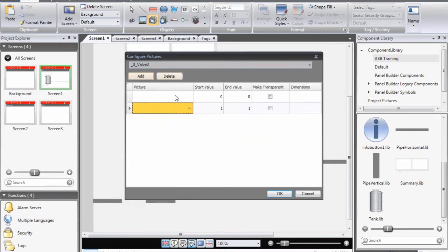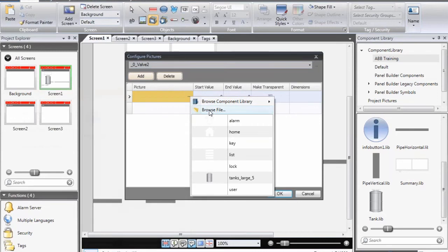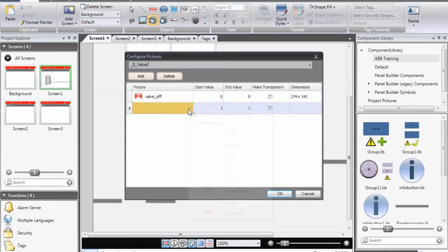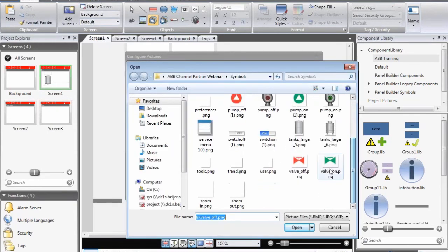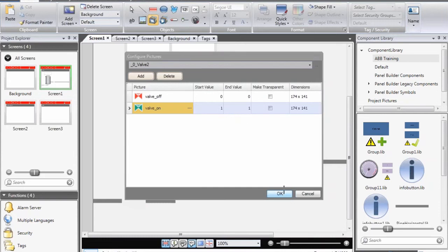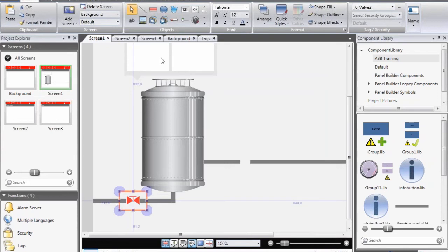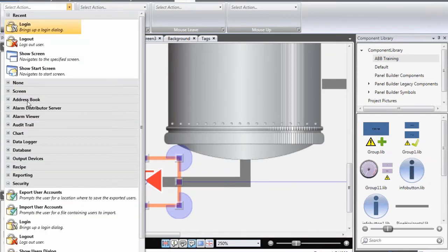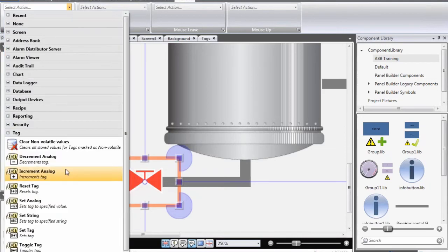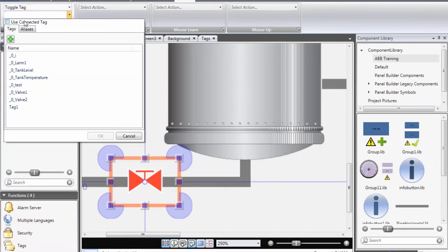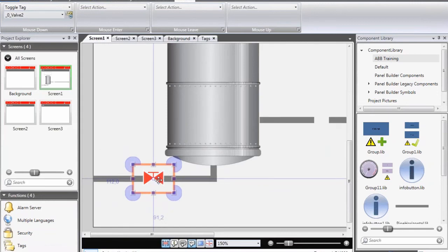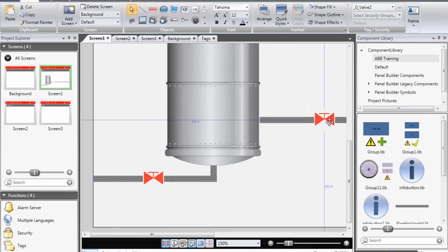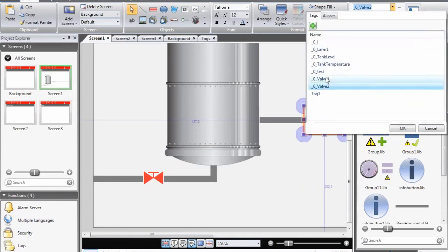I need to first define which tag should control which picture is displayed. I select valve 2, add a picture, and browse for a file. I select valve off — this picture will be shown when the tag value is 0. Then I select valve on, and it will be displayed when the value of the tag is 1. I adjust the location slightly. We also give the operator the ability to control the valve by assigning an action. In this case it will be a tag action, so when the operator clicks on the object, we will toggle the tag that controls which picture is displayed. I then copy and paste the valve, simply replacing the tag connection with valve 1.